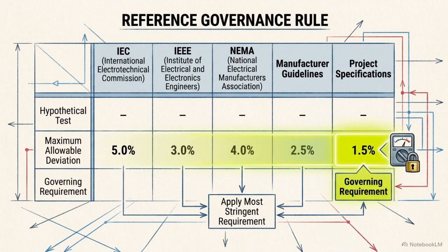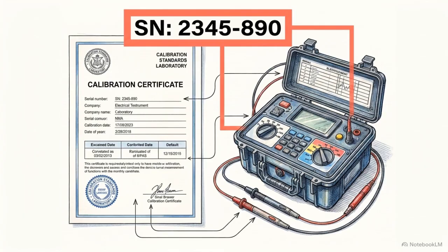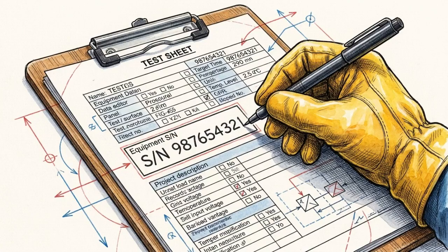When project specifications, manufacturer guidelines, and international standards differ, the rule of governance is absolute. Apply the most stringent requirement. Because this data forms a permanent legal record, the instruments themselves must carry current calibration certificates. Every test sheet requires the traceable serial number of the exact device used to generate the reading.